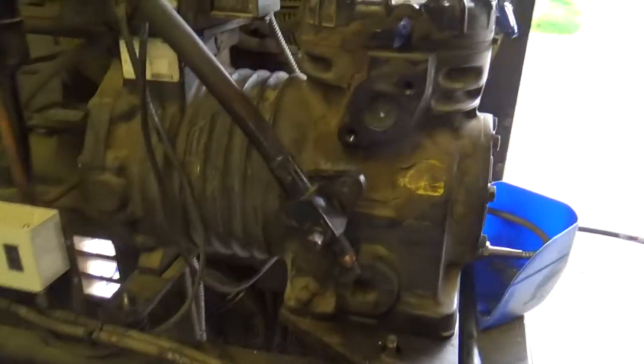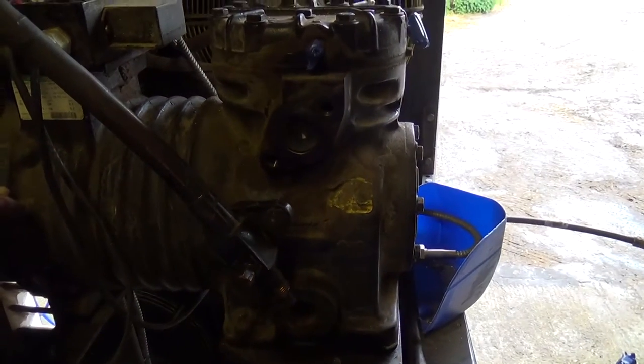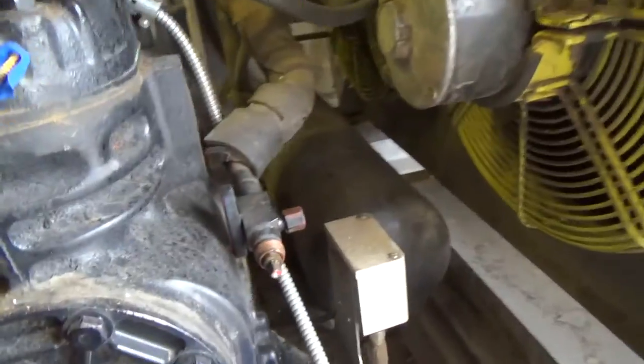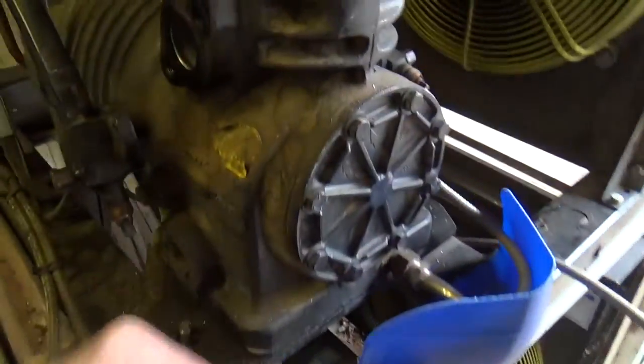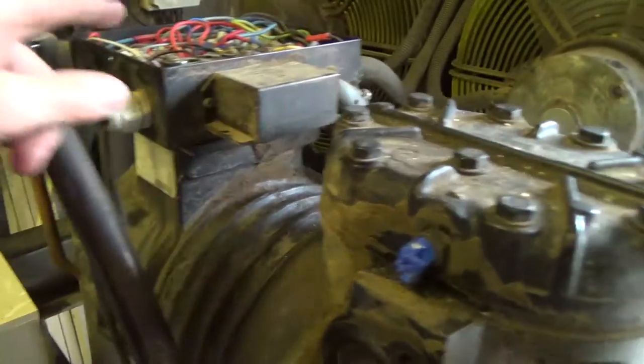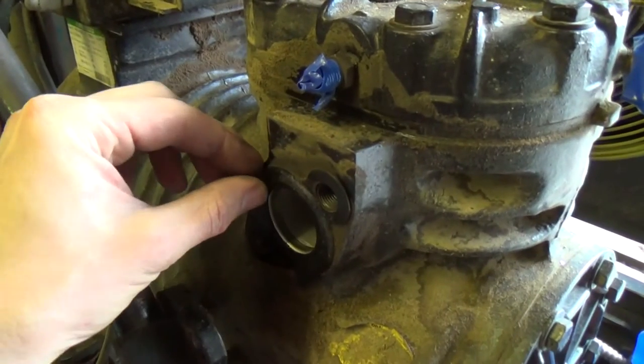Back out, changing this compressor. Got the gas taken care of it. Shut off on these valves. It's unbolted. Got the pressure lines disconnected and taped up so we don't get any crap in there. Just got to take all the wiring out of there. Check it's dead, obviously.